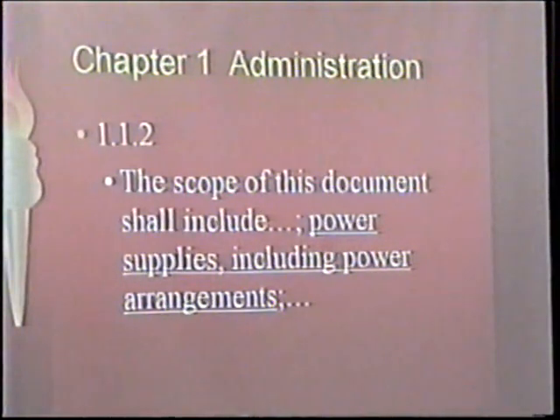So what 20's done is they've brought in a lot of the stuff out of 695 into 20. They haven't taken it out of 695. It's just they brought it in so that the design people hopefully will become more aware of what the electrical requirements side is. Because it's always been a coordination effort when you get into the design firms. It's been, this is mechanical's territory, and for some reason they don't talk a lot to electrical. They tell them, hey, I got this horsepower motor and I got this voltage, and electrical goes on their way. And they don't necessarily coordinate it properly. And so this is an attempt at NFPA to try to get some of that coordination work done, I think.